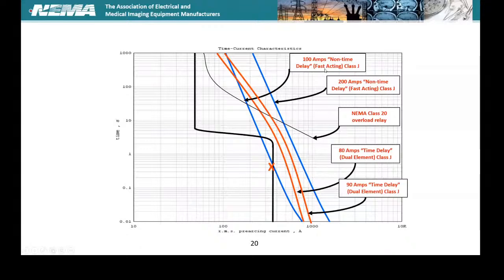So what we look at is the next two fuses. If we have 2 fuses here and one of them is a time delay 80 amp, we get a curve that comes close to this knee, but it doesn't intersect. And of course, it's still good at the full load ampere range way up here. Well, if this is too close and we find that fuse doesn't start the motor, the code allows us to go to the 140%, and we can push that curve out to the 90 amp fuse on the red line on the right-hand side. Yeah, you know, Jack, time delay.